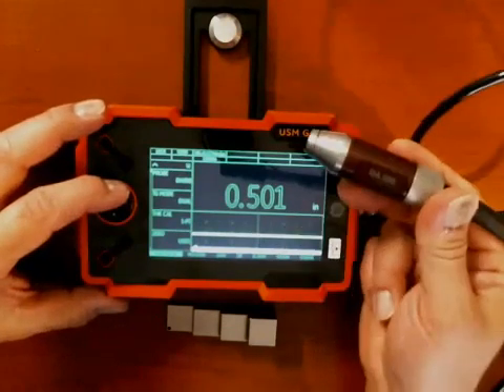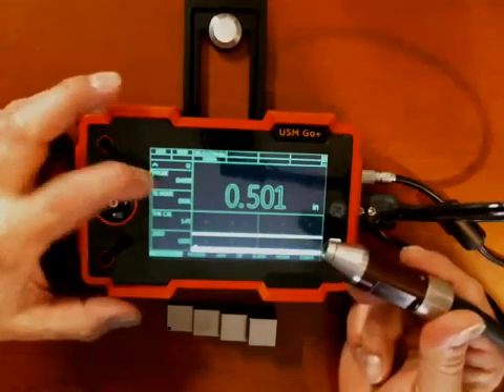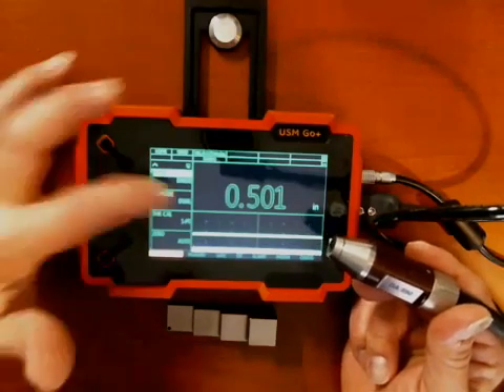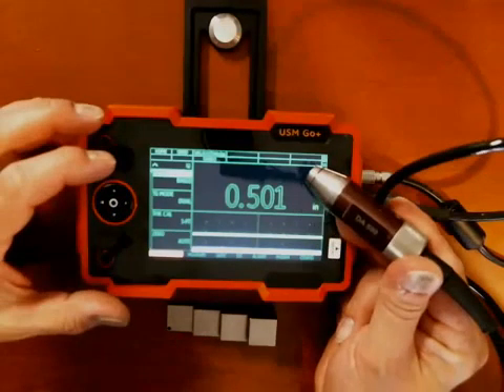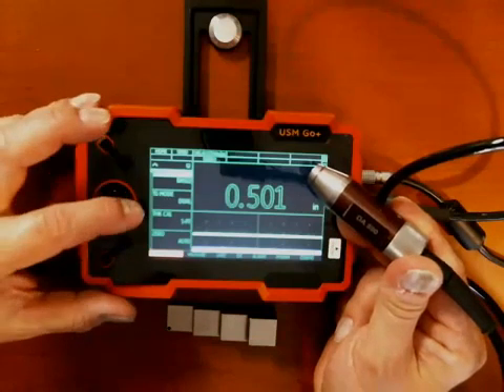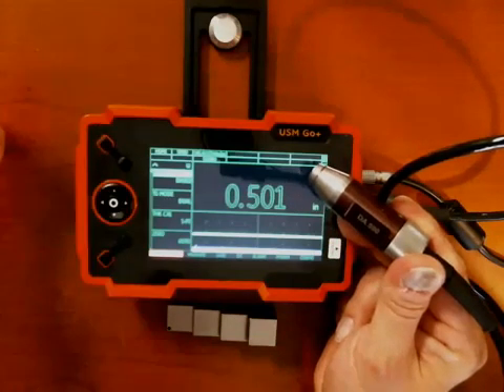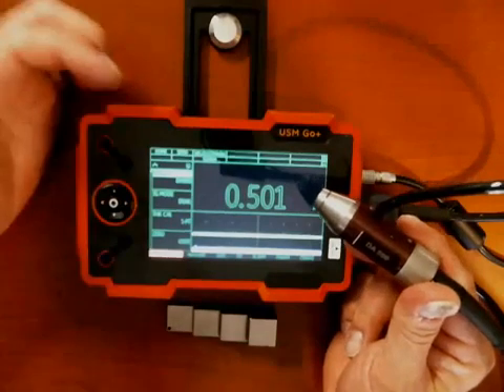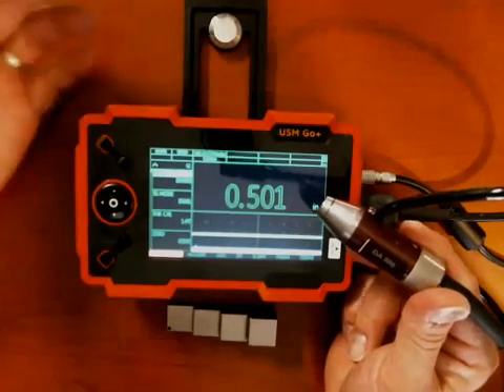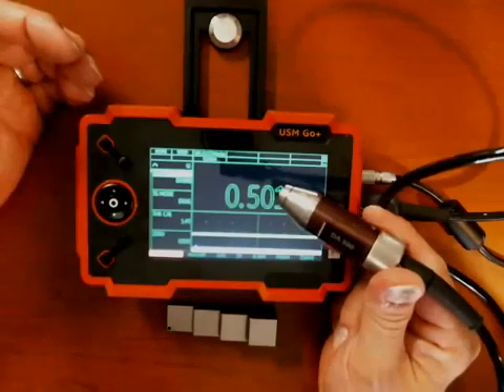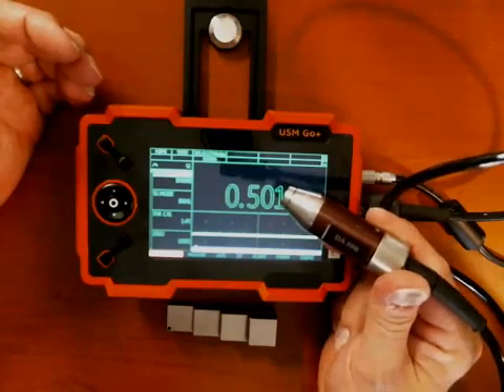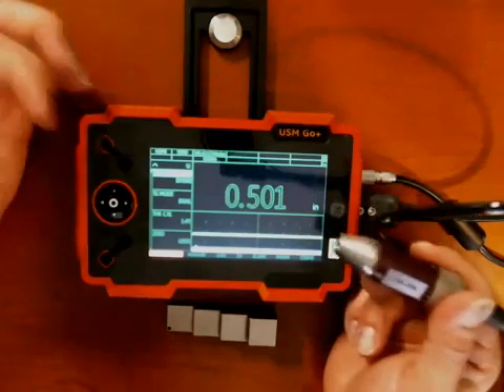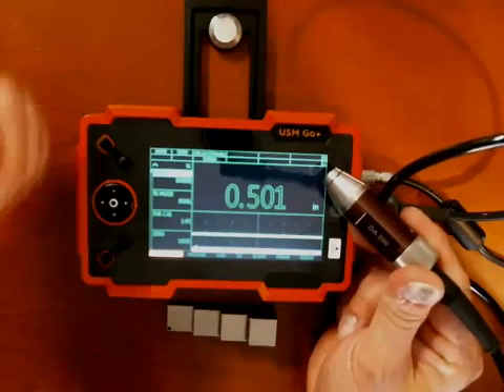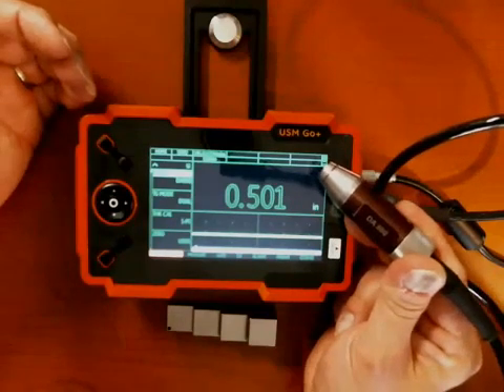Now the next thing I'm going to do is I have a DA590 probe. In this case, I already have DA590 chosen, but let's say I was on something else, like it was set to DA512. It's very important to tell the instrument what probe you have. So I'm going to set that back to DA590. The instrument will set itself up to work well with the type of probe that you just told it you have. So now my instrument should be set to the factory defaults for working with the DA590.